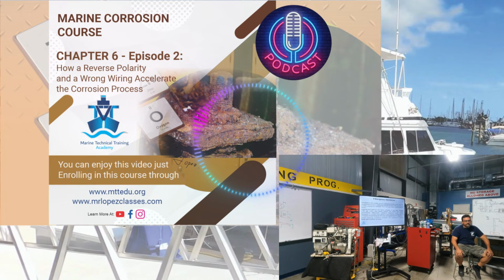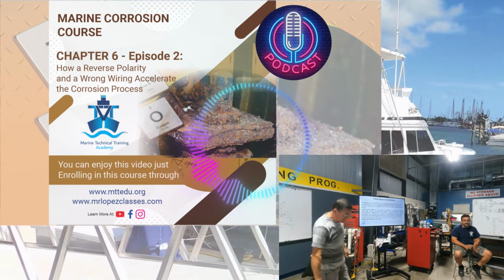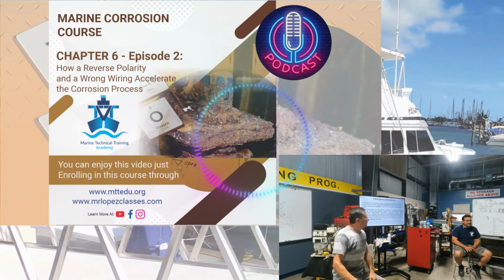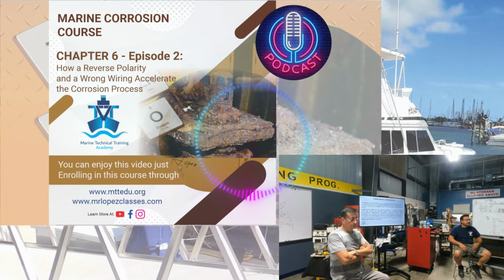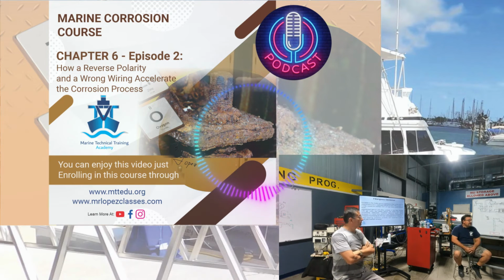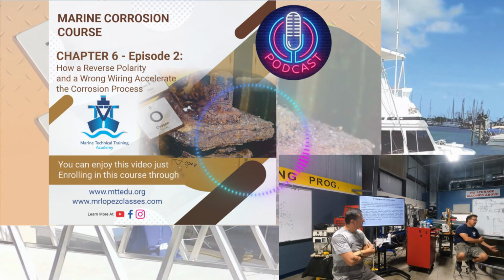Where do you connect the donut? If I want to know the consumption of the whole system, I am going to read on the hotline at the input of the panel, and now I read how many amps are in the consumption. But if I want to check the consumption only of the battery charger, I turn on the breaker of the battery charger and I check here on the hotline of the battery charger. It's only on the hotline to read amps in AC power.